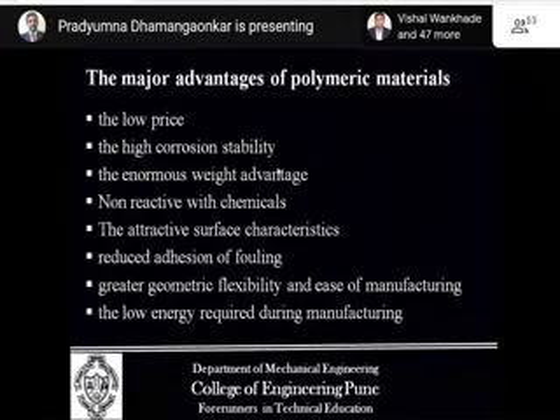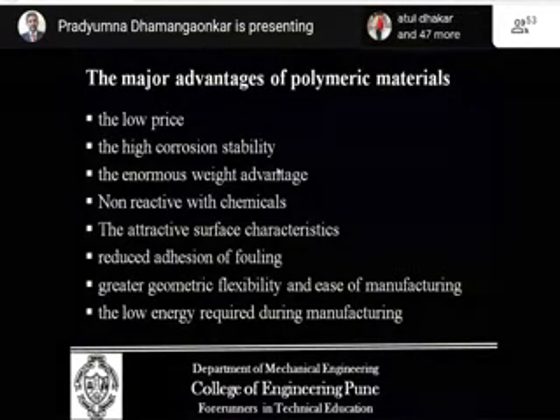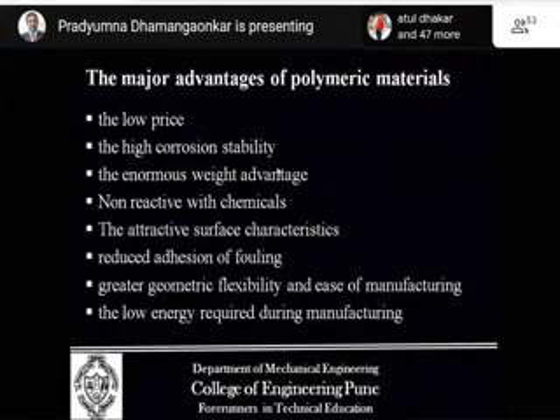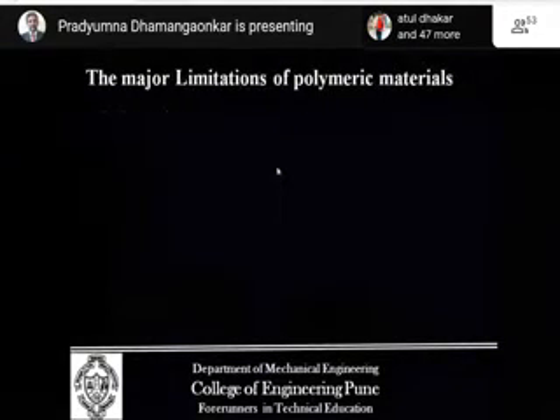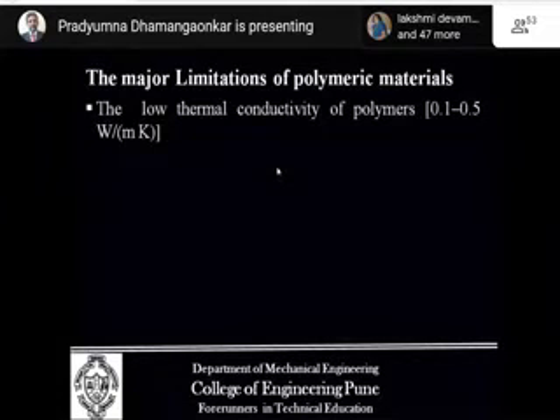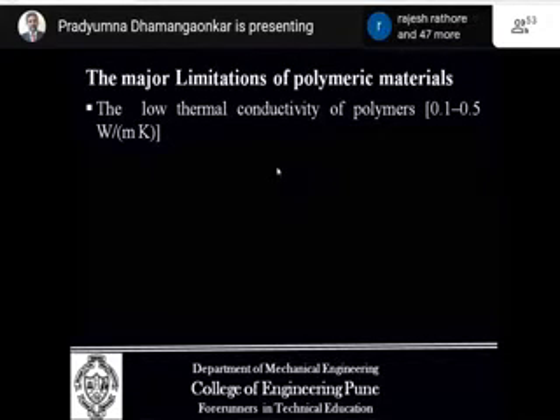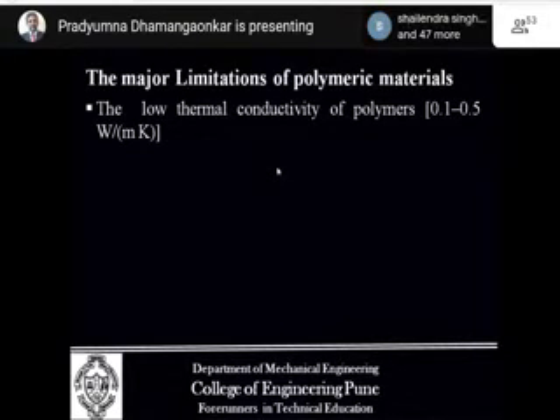It requires low energy during manufacturing as compared to the metal plates. This is feasible, but there are certain basic limitations. These limitations are the low thermal conductivity of polymer. It is hardly 0.1 to 0.5 watt per meter Kelvin. Just think of what is the thermal conductivity of most of the conductive materials, steel or stainless steel, iron or any copper.